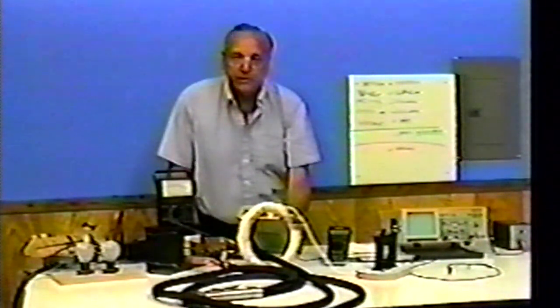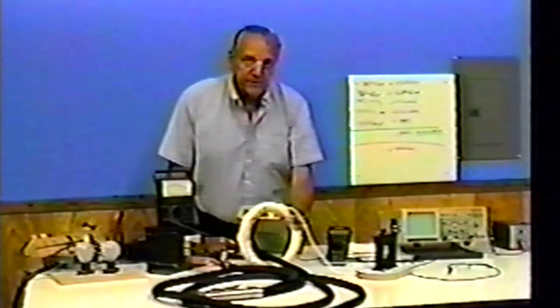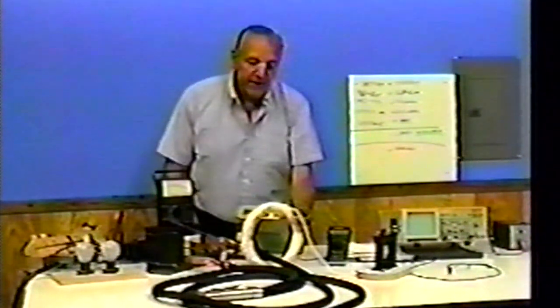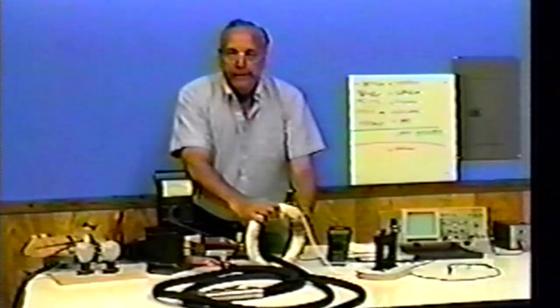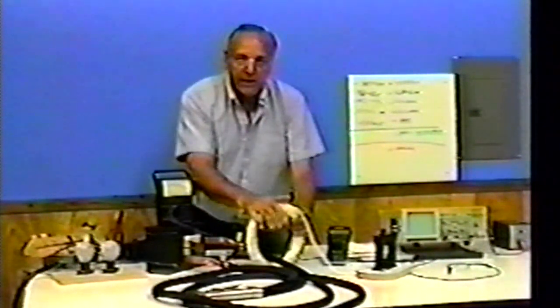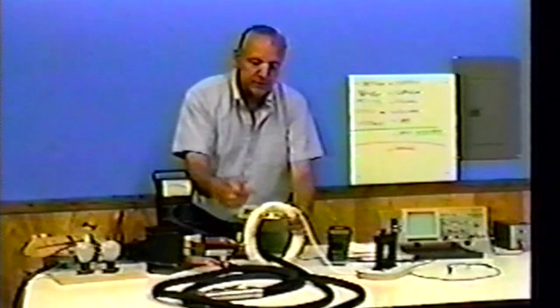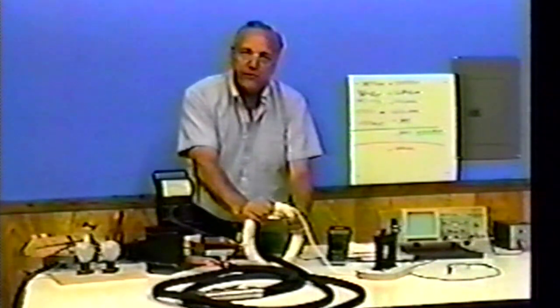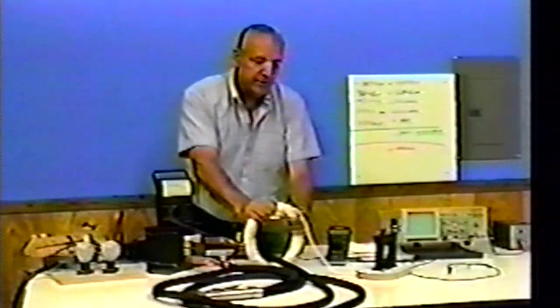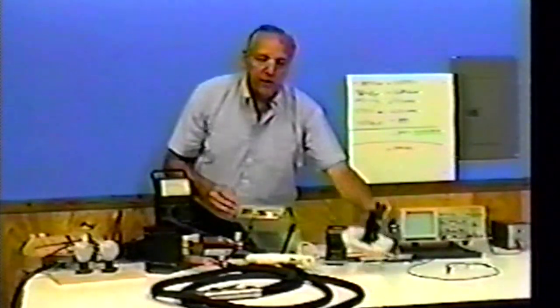Now this device will measure up to 8,000 amperes with a 0.1% accuracy, so this is an extremely accurate thing. It's basically a transformer. There's iron in here and wire wrapped around it, and it's a very, very accurate device.